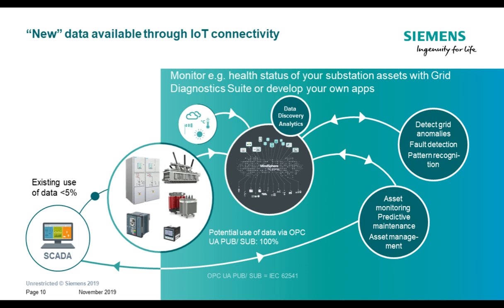If we put in perspective the different architecture levels on the substation, normally on the protection relay, the intelligent electronic devices as represented here, we have 100% of that information. If we go up one level into the substation automation system, only roughly 15% of that data is available. And if we go one level higher to the SCADA, we are already working with less than 5% of the information or data available in the field.